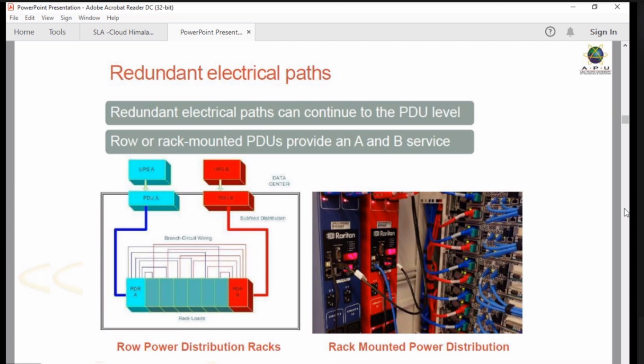If one path has an issue, operation continues with the other path. So you can see here two different paths for utility, and this is the tier 4 system — it's only tier 4 which provides two fully redundant paths. Tier 3 can provide 2 paths, but not redundant — not all components are redundant in tier 3, but in tier 4 all components must be redundant. That's the difference between tier 3 and tier 4.